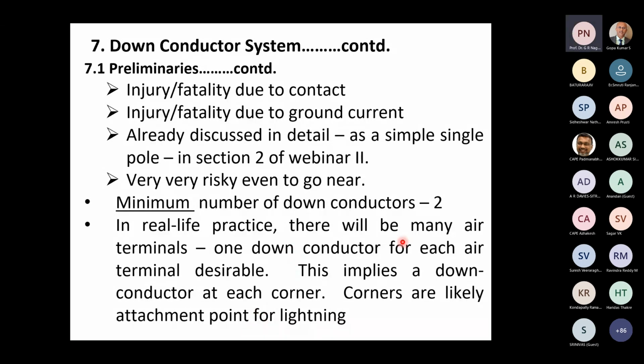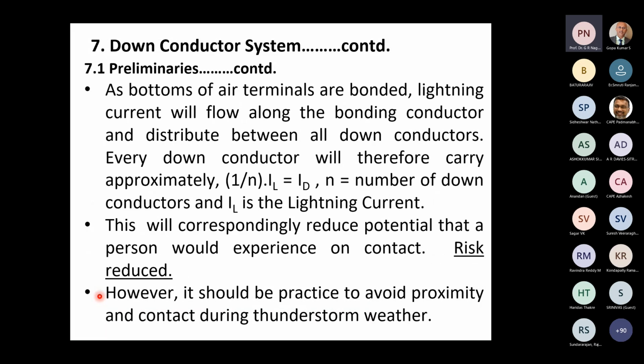So in real life practice, there will be many air terminals. One down conductor for each air terminal is very desirable. Now, as I told you, if safety considerations require, it may be necessary to have more down conductors than the number of Franklin rods also. But this is usually unusual. Still, one has to think of these things also. As I told you, corners and edges are the most likely points.